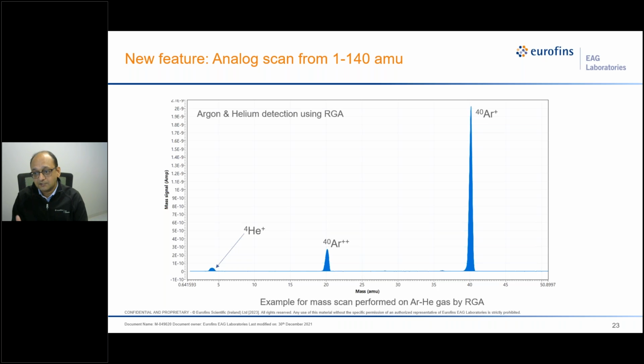In this particular gas, as you can see, we have measured an argon and helium combination. It's a standard gas for helium and argon that we have analyzed, and the helium-4 peak is seen, as well as argon-40, which is the primary argon peak. But you can see that argon-40, when doubly ionized, has a mass-to-charge ratio around 20, so we can see that secondary peak for argon. One has to be very careful that it cannot be interpreted as neon-20. This is the calibration we used, so we know exactly how much of mass 20 is coming from argon, and then how to calculate neon gas.